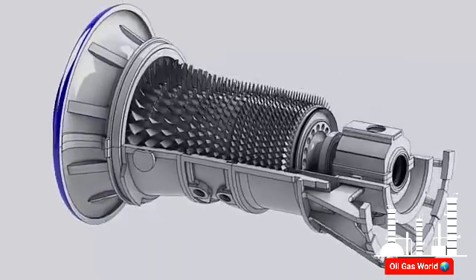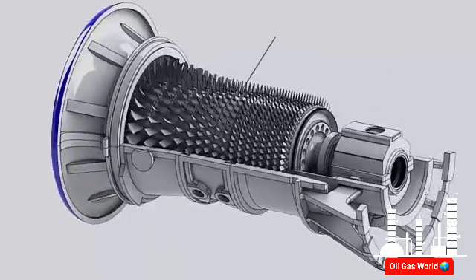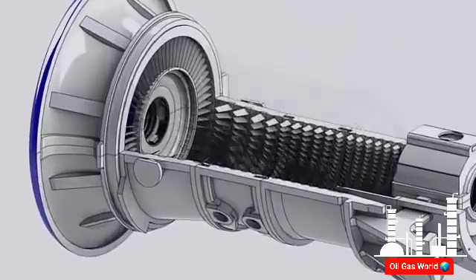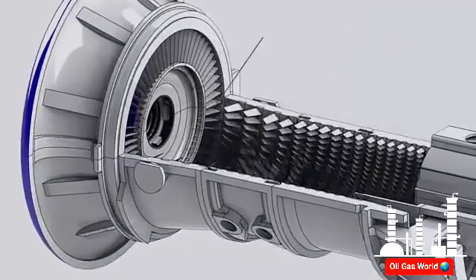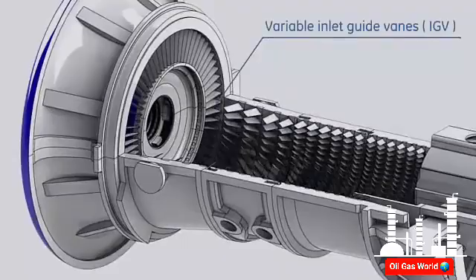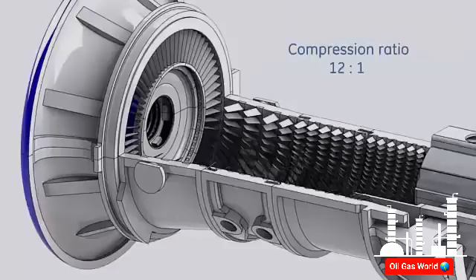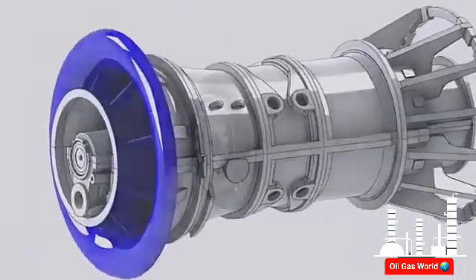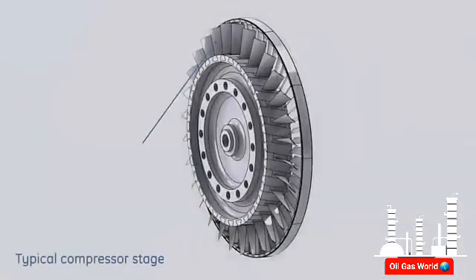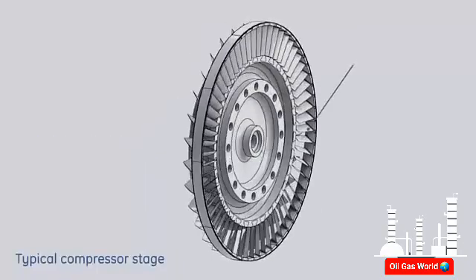The compressor is a 17-stage axial flow compressor with variable inlet guide vanes. Air is compressed to a pressure ratio of 12 to 1. Each stage consists of a set of rotating blades and a set of stationary stator blades.